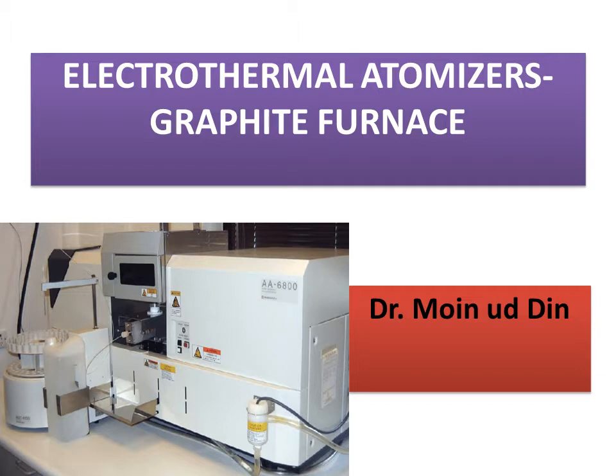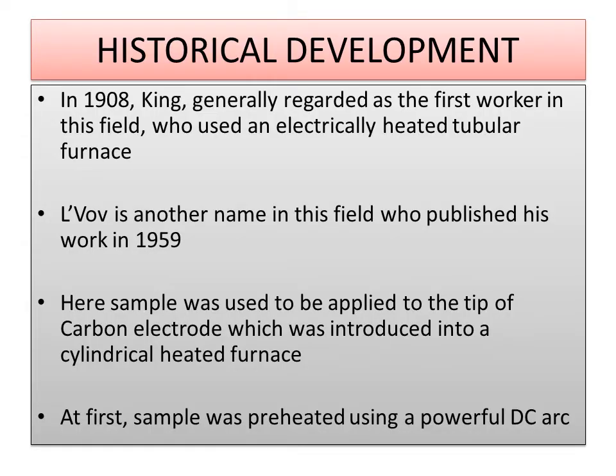In this video we will specifically discuss electrothermal atomizers. Let's start with the historical development, because if we see the history deeply, we can find a large number of modifications made to reach the final shape practiced today. In 1908, King is generally regarded as the first worker in this field, who used an electrically heated tubular furnace.